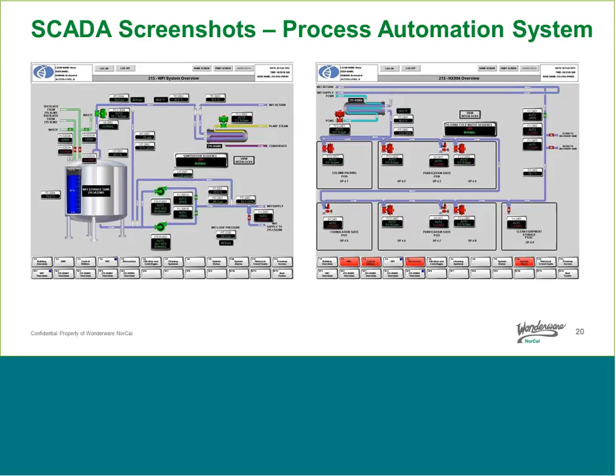This took process chill water, and whether the point of use points, POU, needed hot or cold water, there's a set point above the temperature right next to the heat exchanger. They could adjust it to see if that loop dedicated to that heat exchanger needed hot or cold water, and effectively all drops on that loop would change to a separate temperature set point. There are different interlocks for each heat exchanger drop, not allowing certain valves to open if another valve was in use, because we wanted to maintain pressure and flow through the loop.